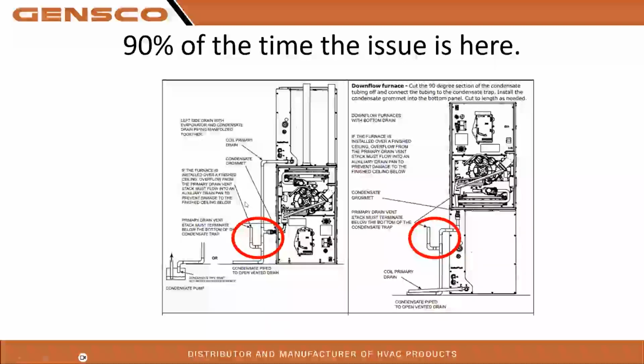Okay. You have to have an atmospheric vent coming right out of that furnace. So as it comes down, however you bring it out, whether it's sidewall or down to the base in this downflow model, we've got to have an atmospheric vent here. But also remember, if you have a random trip on a windy day, it's because of that wind, right? It's putting air through that heat exchanger system and that switch is noticing it. So that's an intermittent 9.1, right? But 90% of the time, it's the installers forgetting to put this dog leg in there and actually vent to the atmosphere.